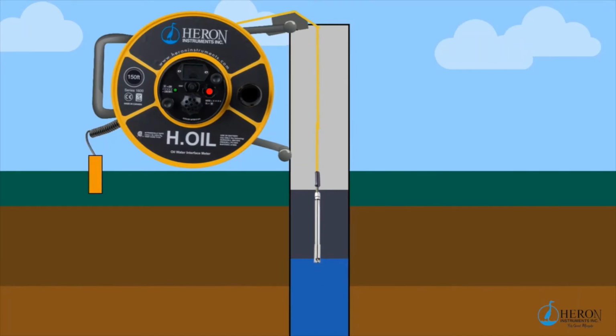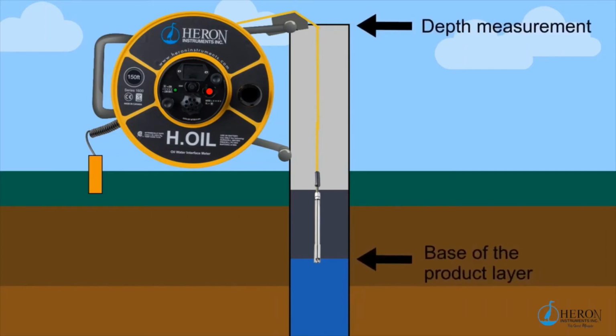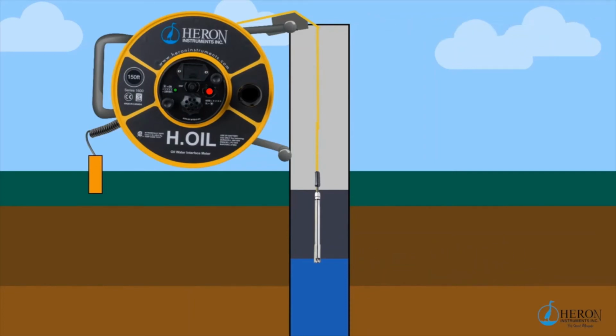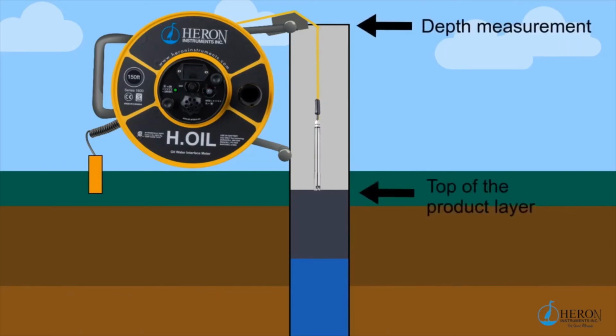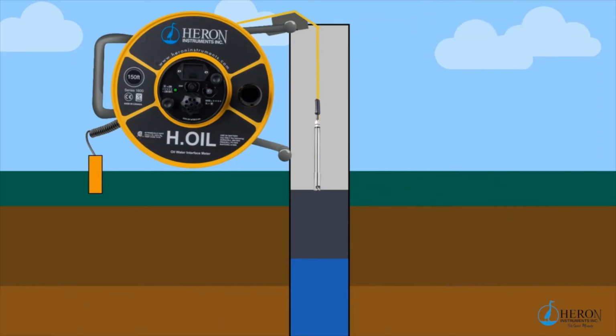This point indicates the base of the product layer. Note the depth marking on the tape. This method avoids having the product drawn down into the water, giving false interface readings. Continue bringing up the probe until the unit is silent. Note the depth marking on the tape. This will provide you with the full measurement of floating LNAPL product.